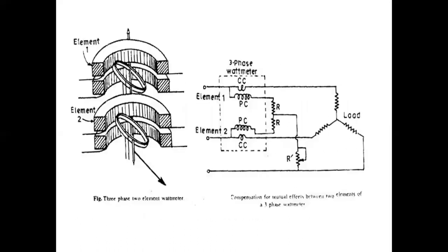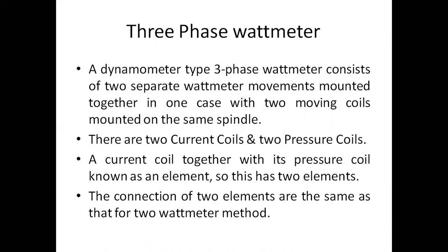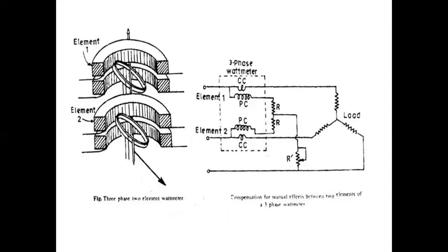There are two current coils and two pressure coils. Looking at the diagram, the first part and the second part represent the two single-phase watt meters connected on the same spindle. A current coil together with its pressure coil is known as an element, so this instrument has two elements. The connection of the two elements is the same as the two watt meter method — the current coils are connected to the load and the pressure coils are joined together and connected to the third phase.